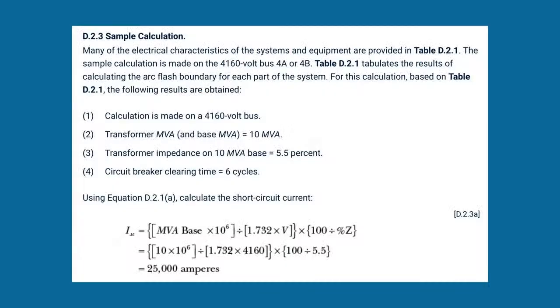Now, here's a sample calculation made on a 4160 volt bus. This calculation is going to be different from the other calculations we'll look at in a second. I wanted to show this because people have called us on how to do this before, when they had software calculating it, and we would go through and explain it. You have your transformer rated at 10 MVA with an impedance of 5.5%. There are always two pieces of information you need to know, and one of them is definitely the clearing time.